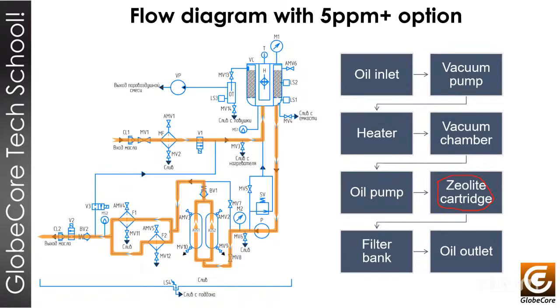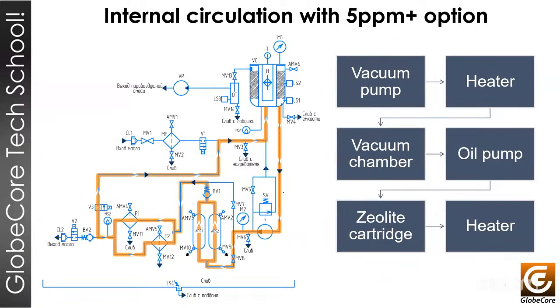But you will select whether to use these filters or not. And another possibility you will have with this machine is the inside recirculation of the oil. If you want to work by batches, that means you will work with one specific amount of oil, and you will make this oil come into the machine again for filtration if you think you need more dehydration for the oil you are working on at that moment.